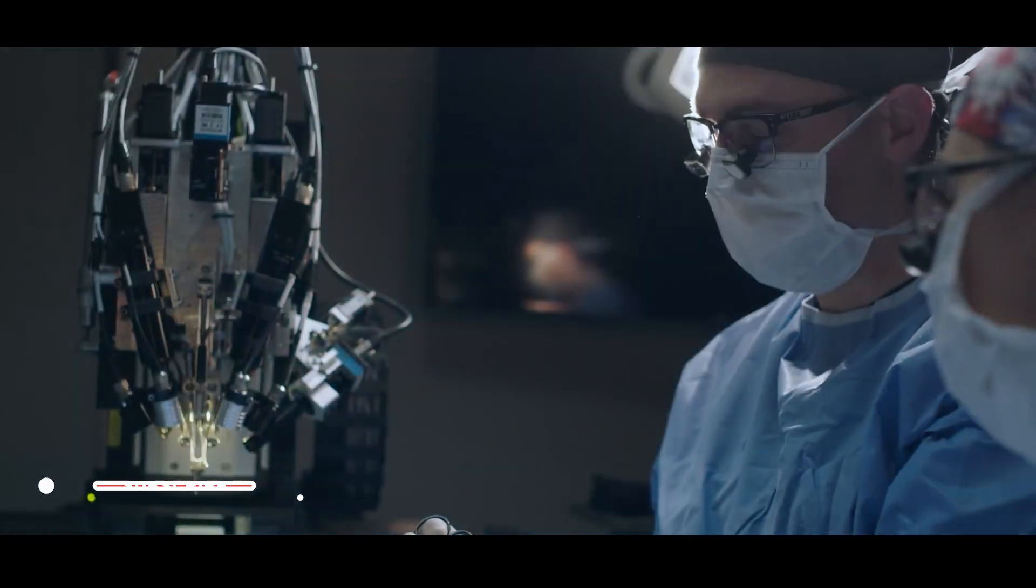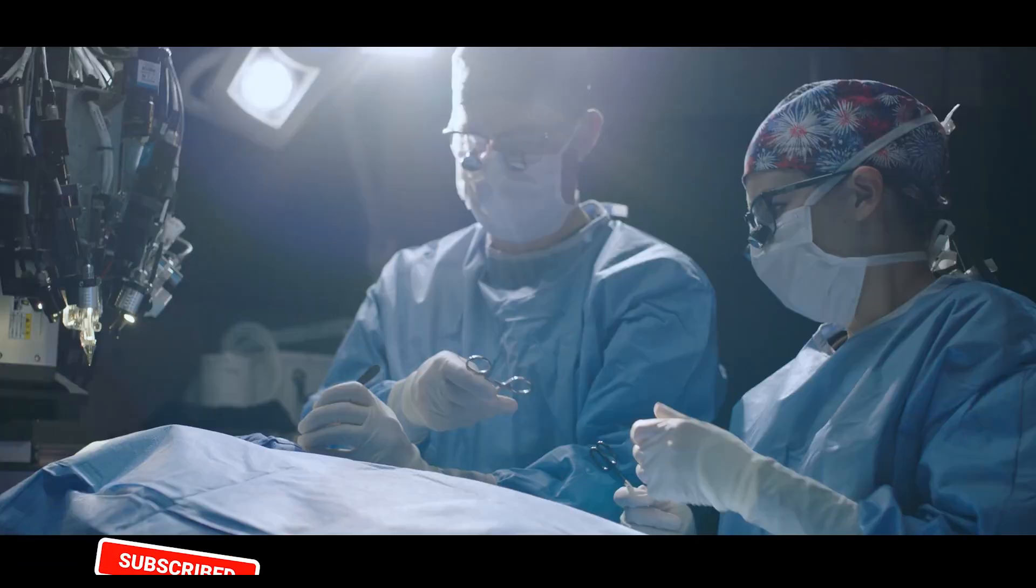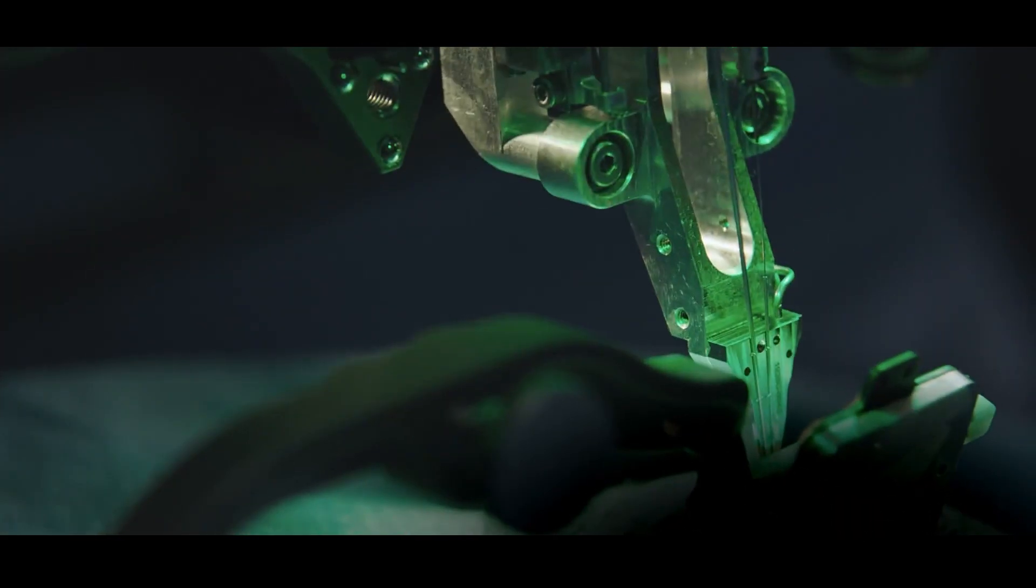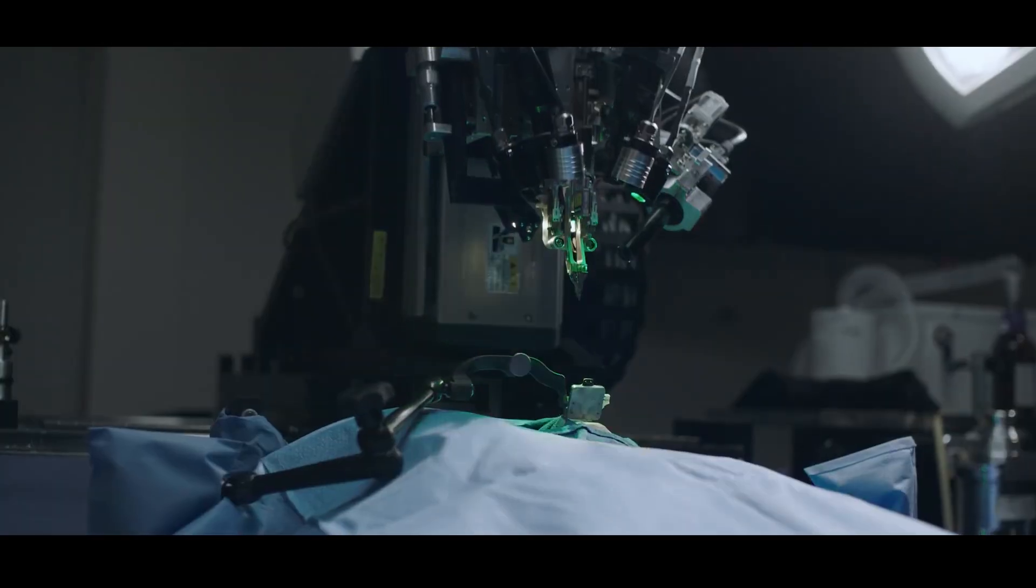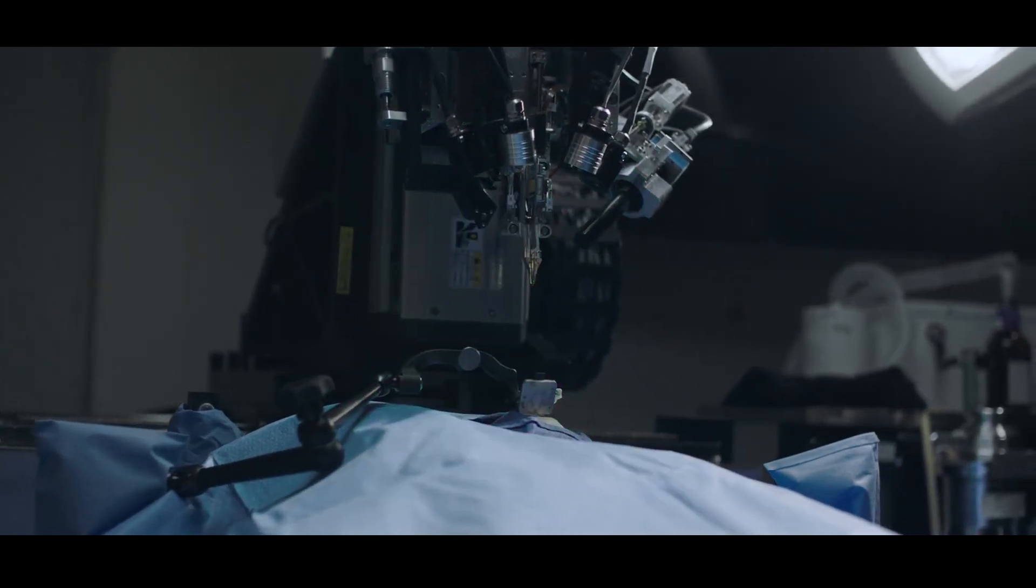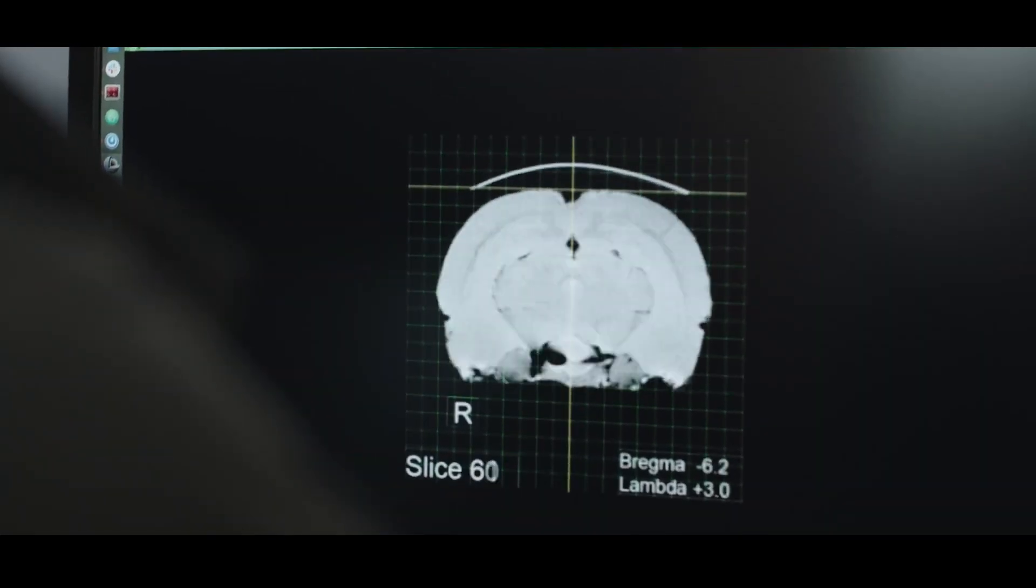Additionally, the business extends that by subjecting its product to accelerated lifetime testing, which involves running the device through a hostile environment with high temperatures and aggressive movement before placing it in a simulated brain environment that replicates the chemistry of brain tissue and bodily fluids. They can obtain an acceleration factor of at least four times by inserting the implant device into this rig.